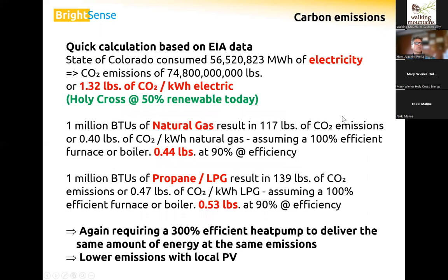Quickly on the carbon emissions, the Colorado average in 2019 was 1.3 pounds of carbon per kilowatt hour electric versus natural gas, 0.4 pounds, propane, 0.5 pounds. So again, a 300% efficient heat pump, or a COP of 3, would give us an advantage on the carbon emissions. Holy Cross is significantly better, I learned. It has significantly lower carbon emissions per kilowatt hour electric. So as a Holy Cross customer, you're already in better shape than the rest of Colorado. If you have your own solar PV system generating your own renewable energy, obviously your emissions would be even lower than that.